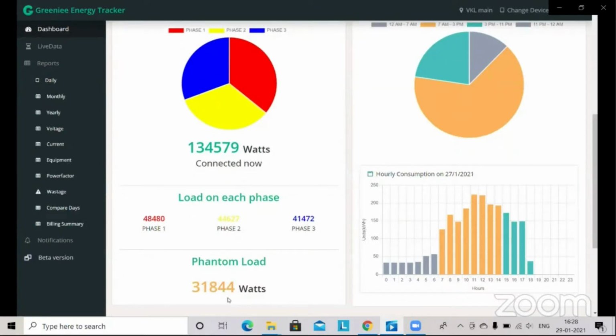Further down, you can see the phantom load. Phantom load is the load which is always on in a premises. This is important because you need to know what loads are always on. For an installation or factory that doesn't work 24 hours, the phantom load should be not more than 5 or 6%.